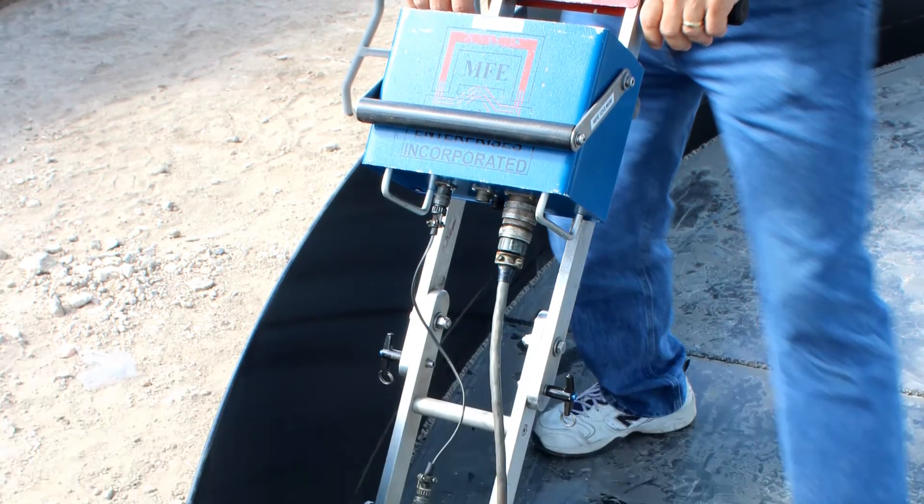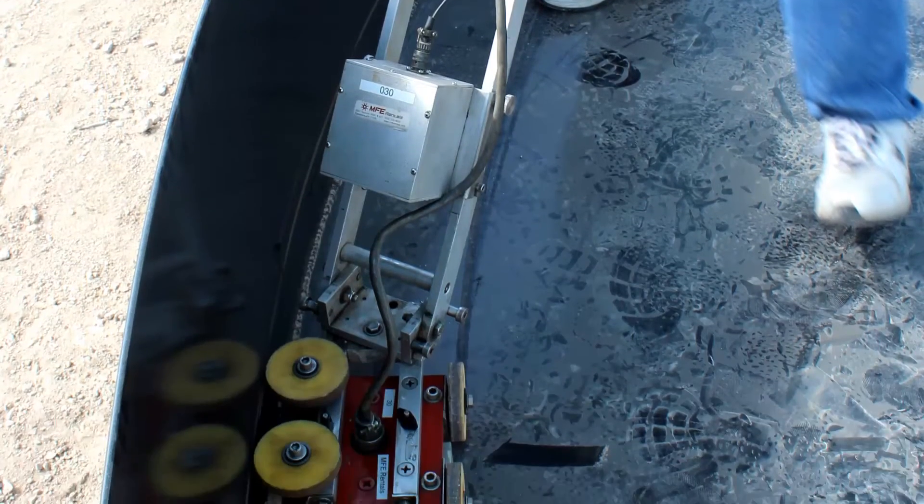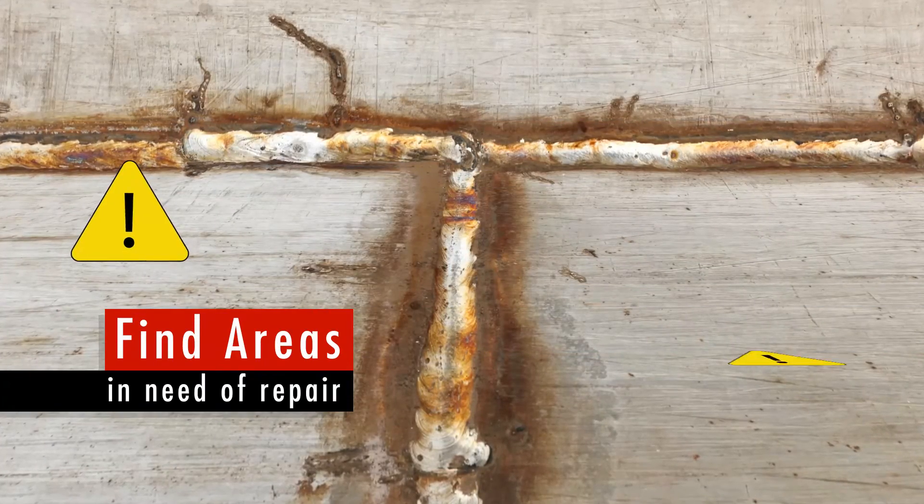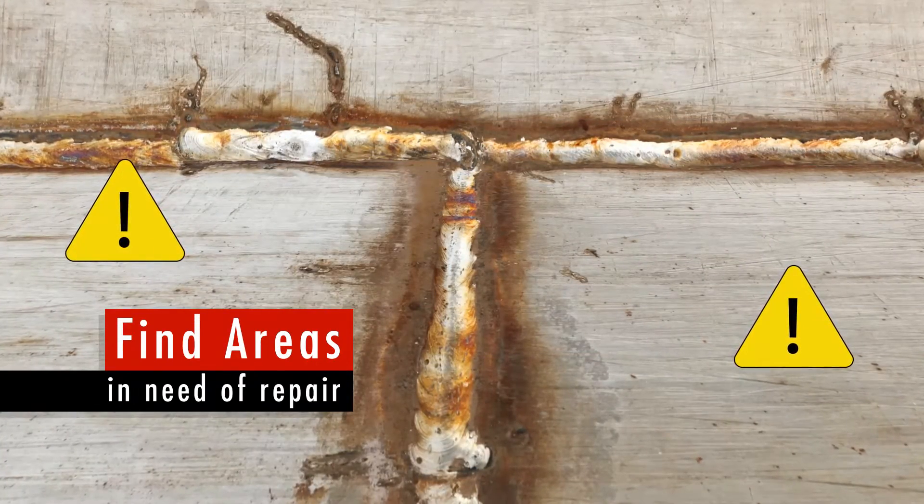The edge scan is designed so that the operator can get close to the tank shell for a fast and accurate inspection of the critical zone, helping find areas in need of repair before they lead to major structural damage.